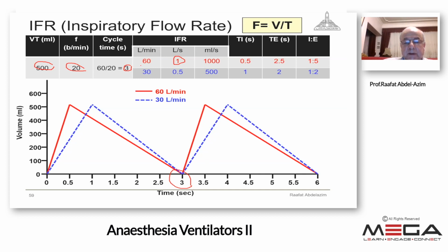The flow rate here, in this example, in the red line, is giving 500 milliliters in half a second, which means it is 1 liter per second. So the inspiratory time is half a second. I don't have the option in this ventilator to adjust the inspiratory time. So if I adjust the inspiratory flow rate by increasing or decreasing, up to the maximum flow rate, I can reach the exact time of inspiration and expiration.